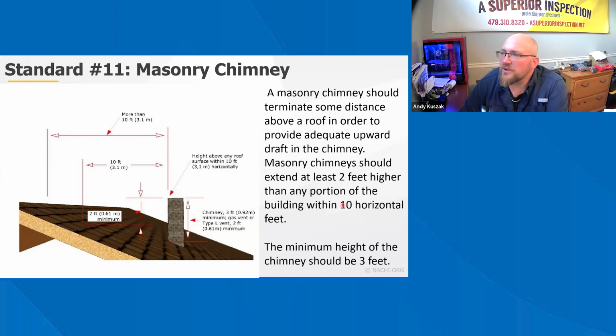All right, so I'm going to go into some details. First, the chimney heights. Existing or older chimneys have been around for a long time, right? So if you have an older home that has a chimney, more than likely it's been there for a while, and you're probably not going to have these clearance issues with an existing chimney, because if it didn't meet specific clearances for the height or whatever, they would have experienced an issue a long time ago, and they probably would have fixed it by now.